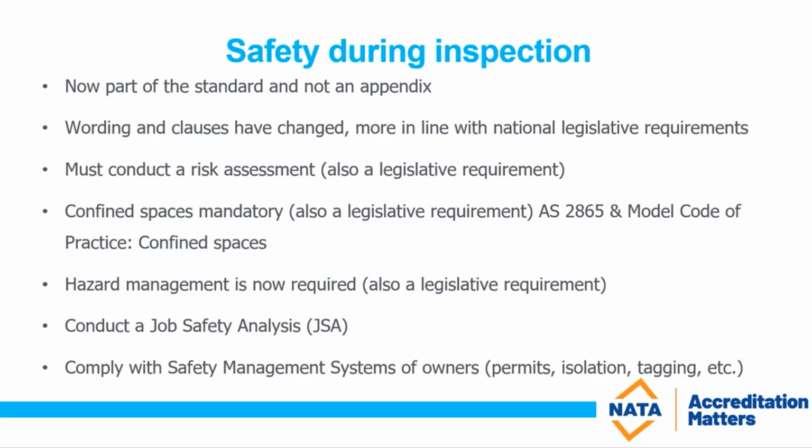For example, there may be gases in a pressure vessel that they may need to ensure is managed, and they need to manage their own safety requirements around pressure vessels that would have that type of contaminated atmosphere inside the vessel. One example comes to mind, which is chrome copper arsenate, which pressure vessels use in curing wood in particular. So inspectors will need to make sure that that is managed and that any residual hazard is equally managed once the main hazards have been removed.